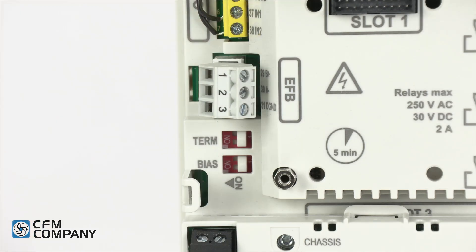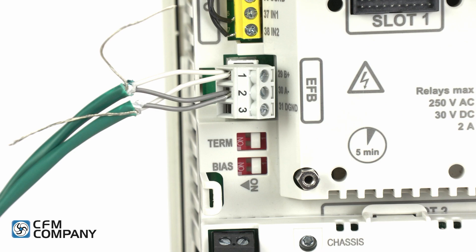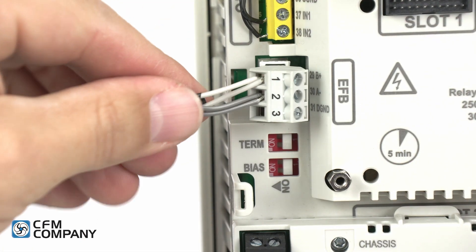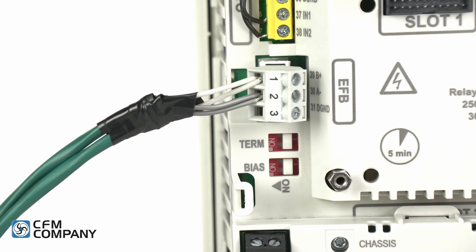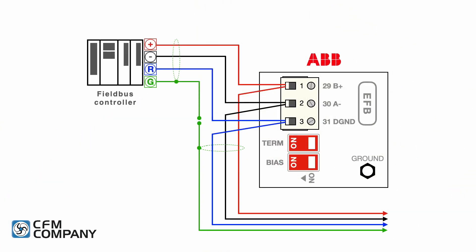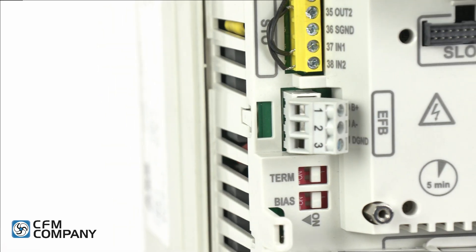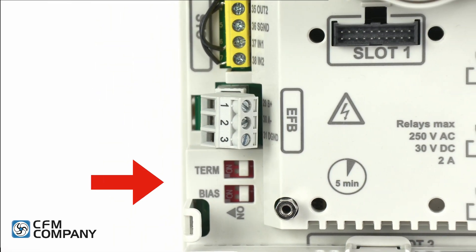For three wire communication networks, connect the optional reference wire to terminal 31 labeled DGND. Note: the network wire shield is not landed to the drive. The wire shield should be twisted together and taped to prevent contact with other conductors.